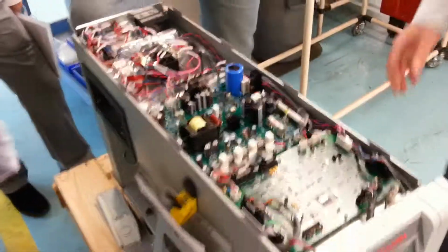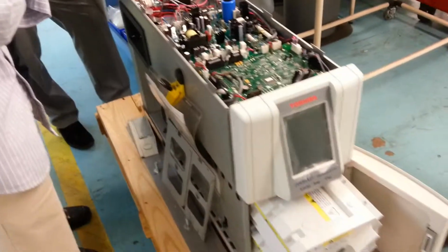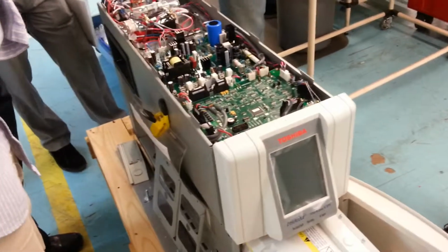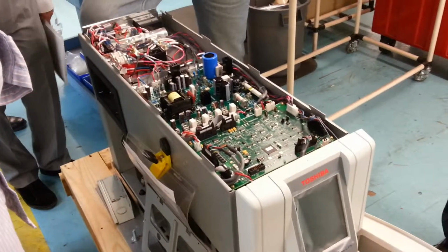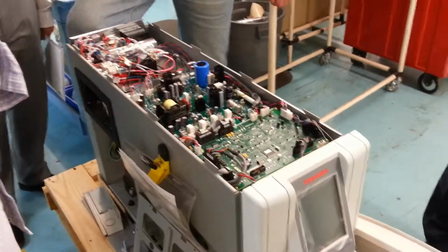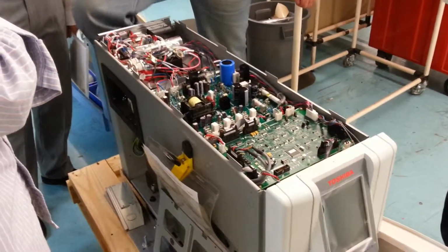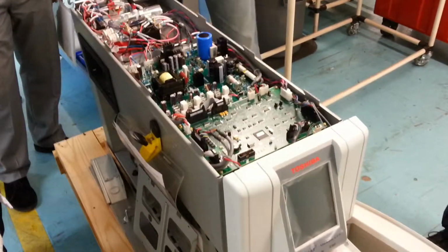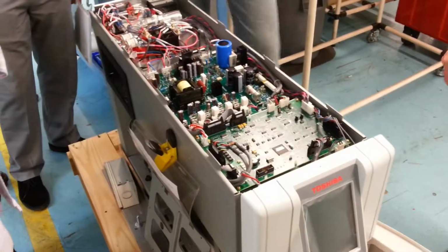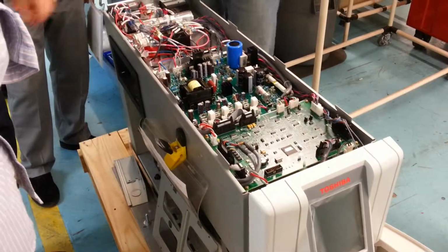Those units go up to 750 kVA and back up the whole building. We can run up to four UPSs in parallel on the big stuff, so four 750 kVA units in parallel works out to about 3,600 amps of total power at 480 volts, depending on the load side.